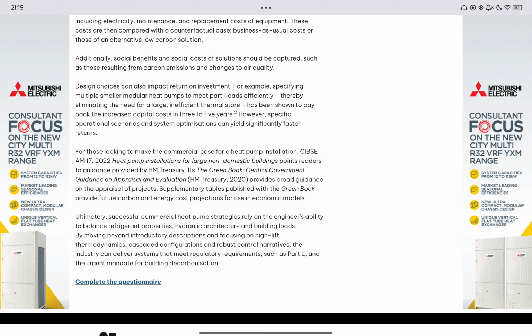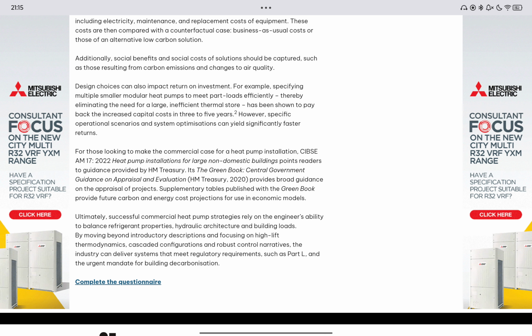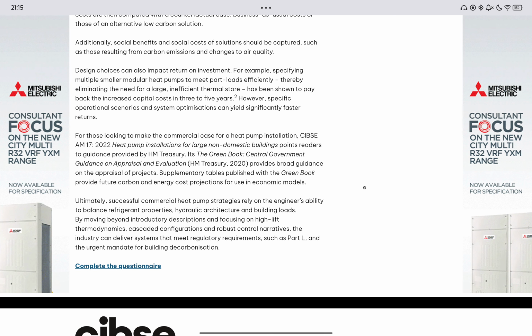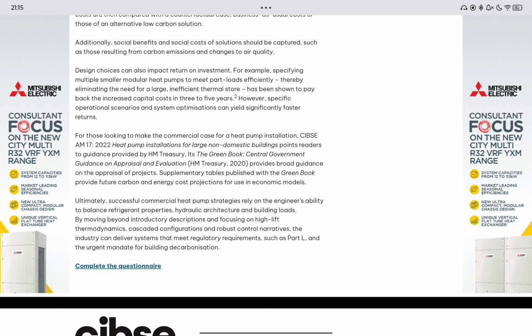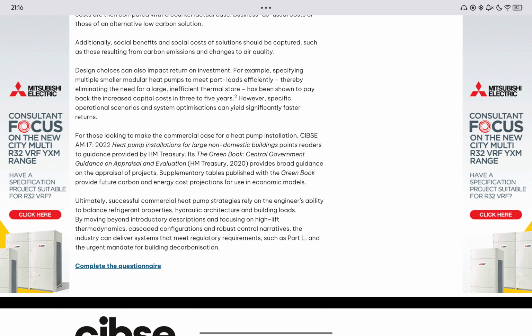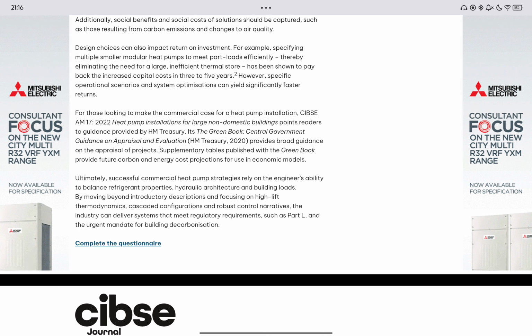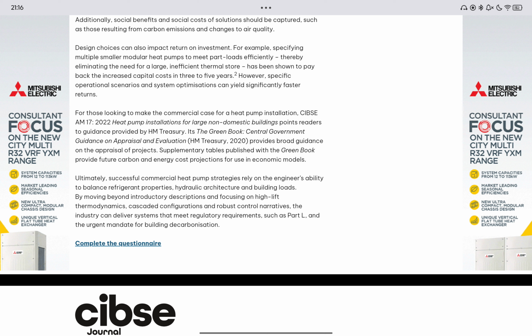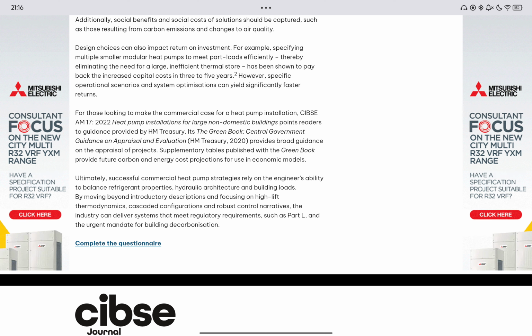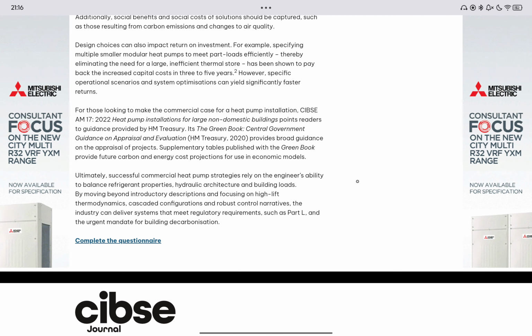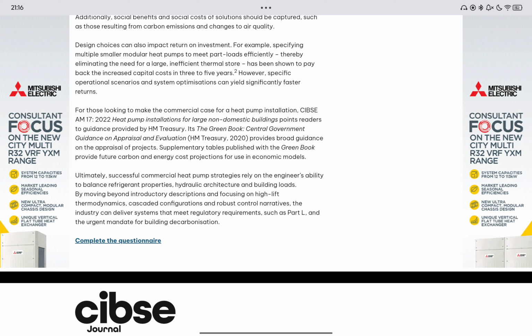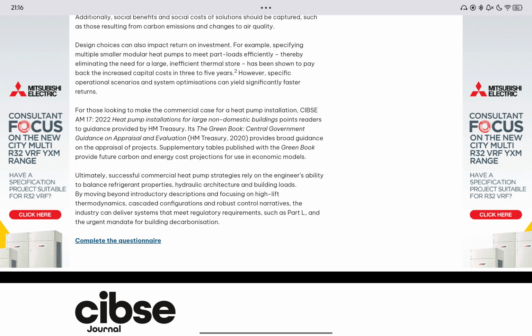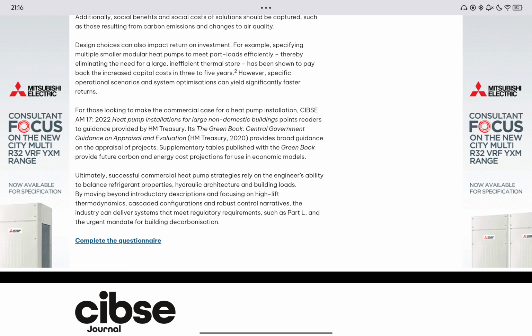For example, specifying multiple smaller modular heat pumps to meet part load efficiencies, thereby eliminating the need for a large, inefficient thermal store, have been shown to pay back the increased capital costs in 3 to 5 years. However, specific operational scenarios and system optimizations can yield significantly faster returns. For those looking to make a commercial case for a heat pump installation, CIBSE AM17 2022 Heat Pump Installations for Large Non-Domestic Buildings points readers to guidance provided by HM Treasury. The Green Book, Central Government Guidance on Appraisal and Evaluation, HM Treasury 2020, provides broad guidance on the appraisal of projects. Supplementary tables published with the Green Book provide future carbon and energy cost projections for use in economic models.